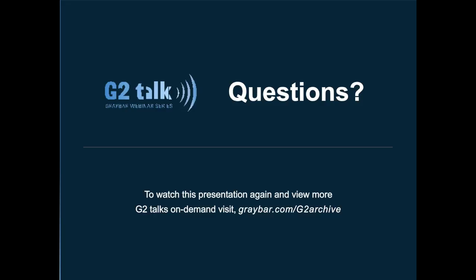Okay, here's a question from James. Did I understand you correctly that I should have a warning label on any equipment if there's 50 volts or more present? Yeah, so again, people start saying, well, geez, that covers a lot of stuff. You might have a disconnect on something that's 120 single phase. Technically, according to the code, yes, that should have a warning label because it's greater than 50 volts, and there is an arc flash risk there, although it's very small. So what I always recommend is to focus on your larger stuff first, and usually I recommend the cutoff at the 3-phase, but even at that, 208 volt 3-phase should have a warning label on it.